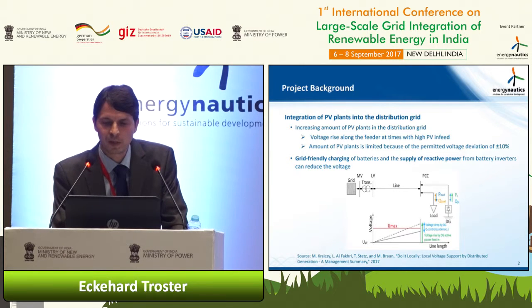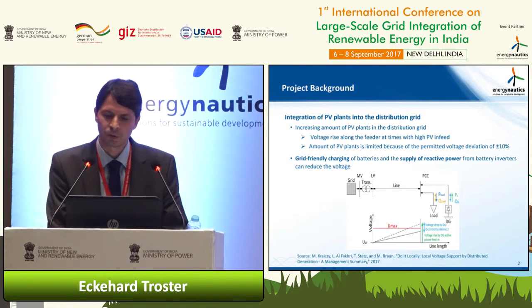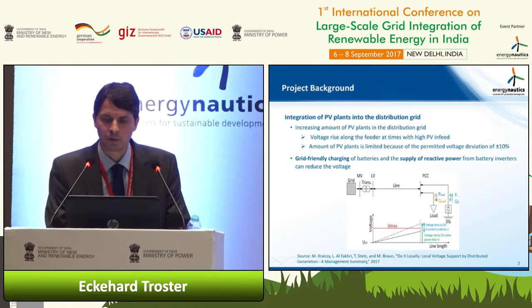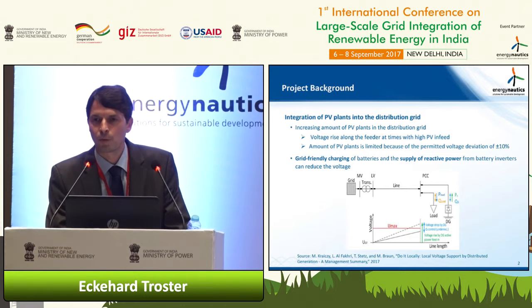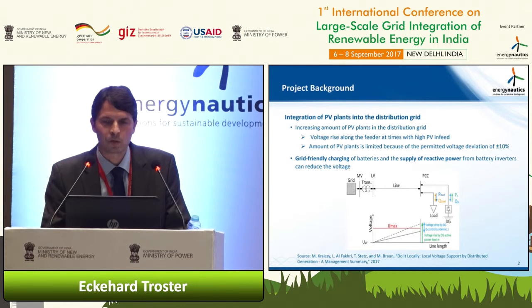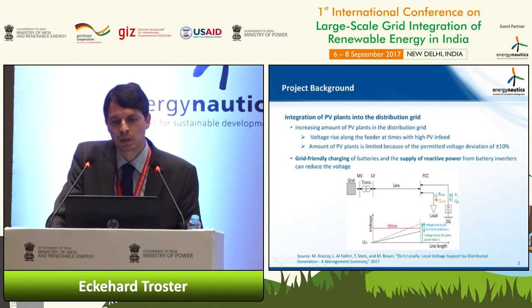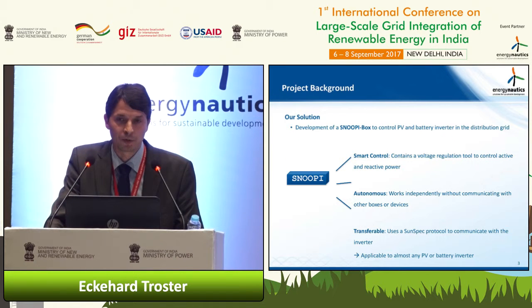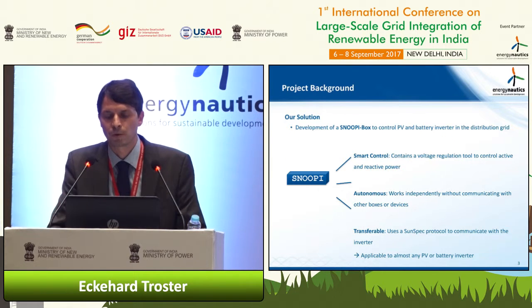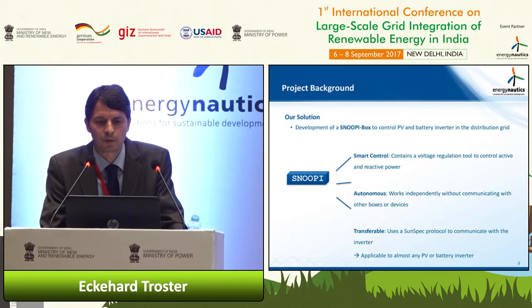So what's the issue? Basically, as soon as we add lots of photovoltaics feeding into the grid, we get a reverse power flow, and with this reverse power flow, we can get overvoltage issues. The idea was to find a device which actually improves the situation and allows for more photovoltaic to be integrated into the system.